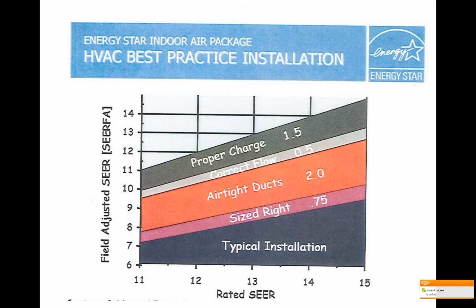When we look at charge just as part of the installation, and we're looking at a 15-SEER system right here at the peak of the graph, let me just pull out a felt tip pen here. At the very top of this graph, if we got 15 SEER out of a 15 SEER piece of equipment, it would be sized right, we'd have airtight ducts, we'd have correct airflow, and we'd have correct charge. And you can see here that correct charge picks up about 1.5 SEER of performance on a piece of equipment. So we're looking at this section of the graph right here. And so correct charge has a very large impact on operation of the equipment.